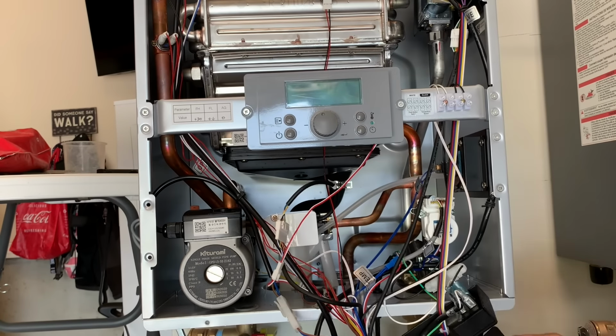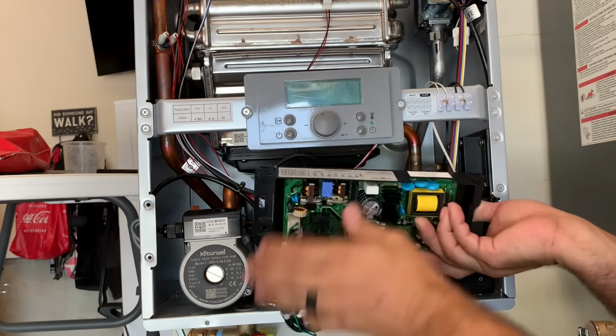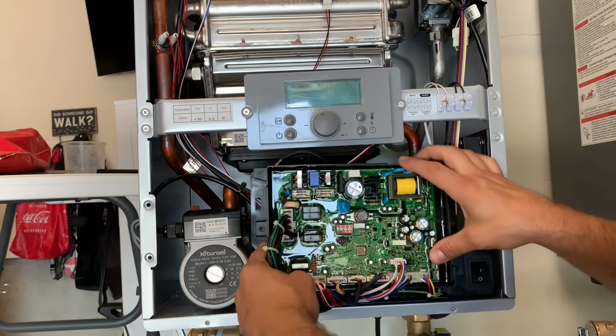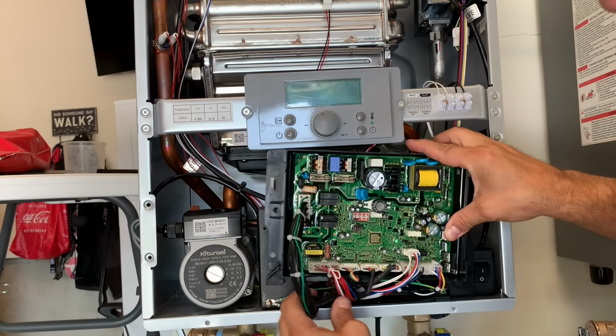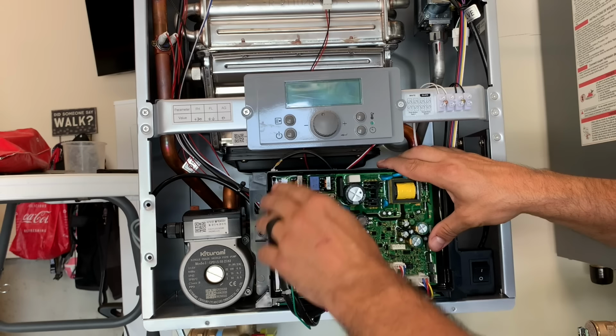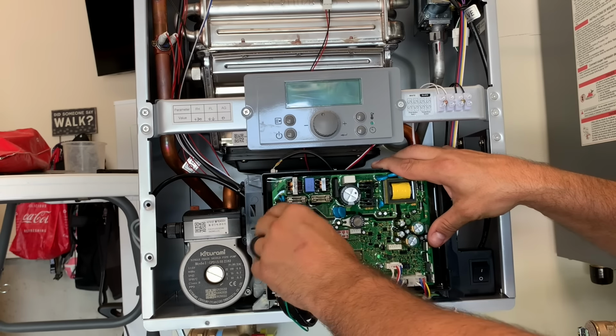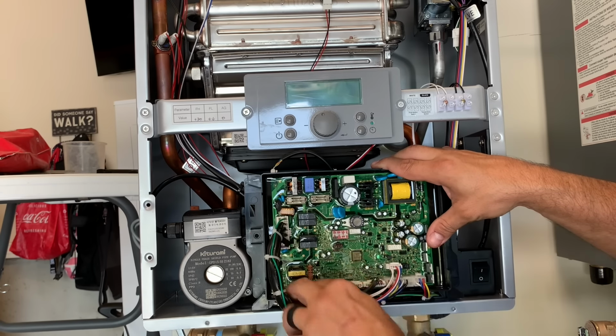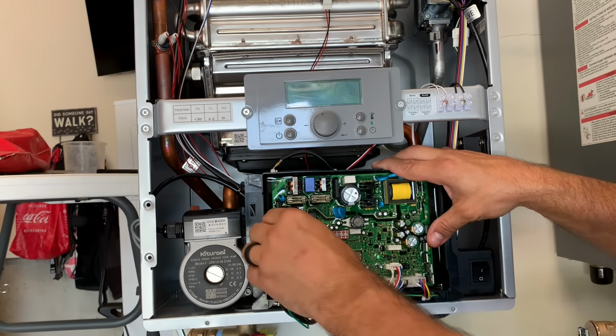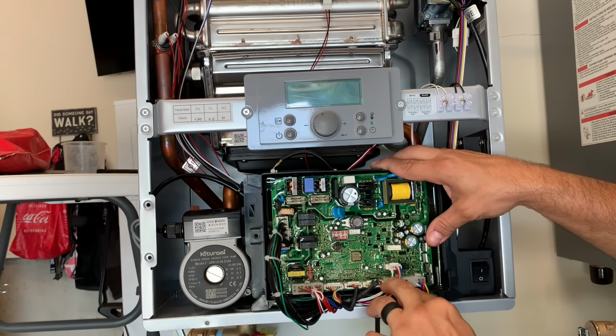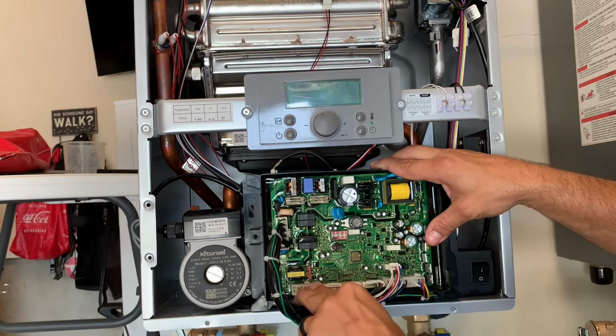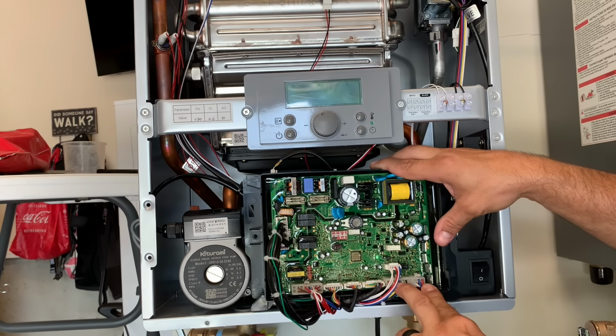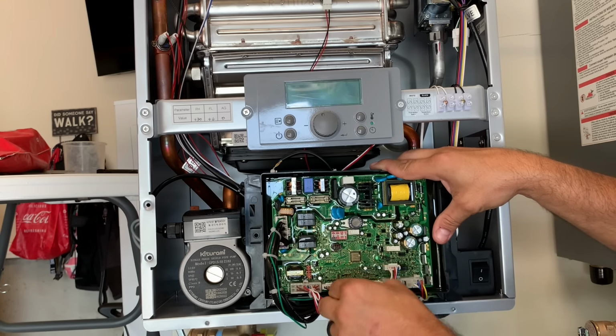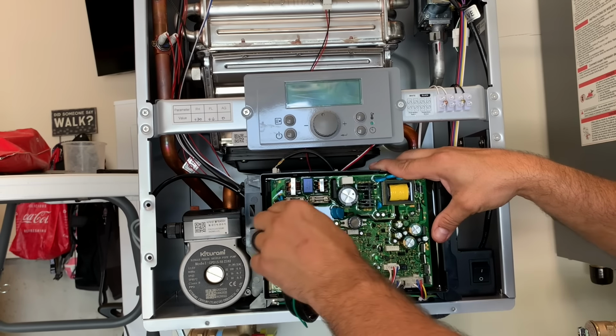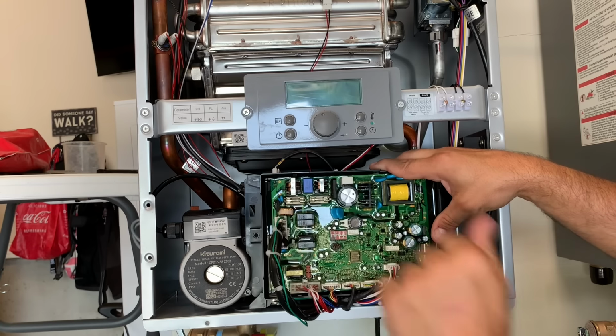Now if you're troubleshooting this water heater and everything is checking out, follow your troubleshooting steps. And if you have to replace this control board, you're going to remove it, unplug all of these wires. You get your new control board, you'll plug those back in. They only go in one spot, so it is hard to mess up. Make sure you have good positive plug in, nice and tight, good connection, and you're good to go.